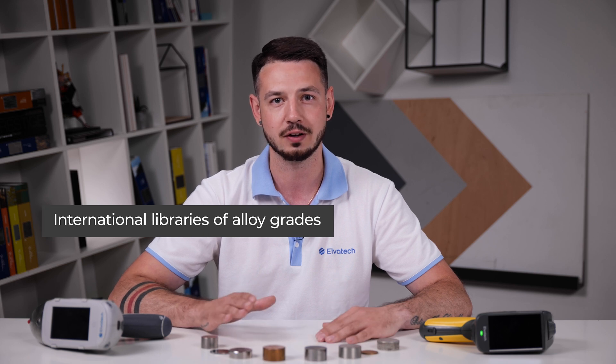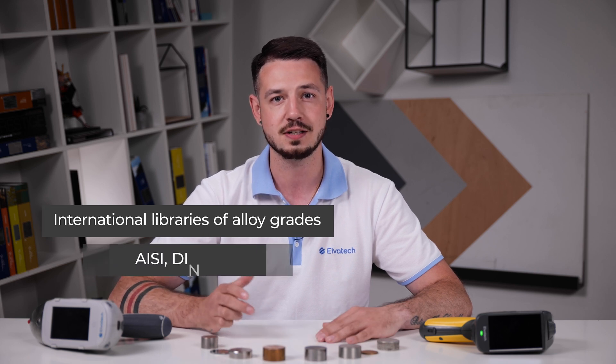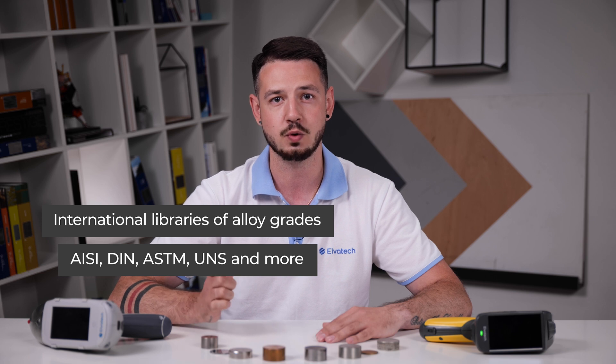Our analyzers have various international libraries of alloy grades, such as AISI, DIN, ASTM, UNS and more. Custom libraries can also be configured that include unique alloy grades used in a particular factory or manufacturing process.